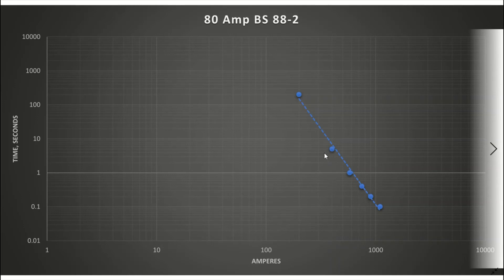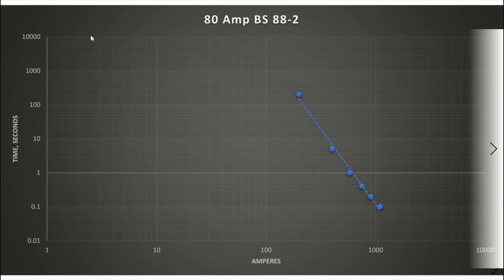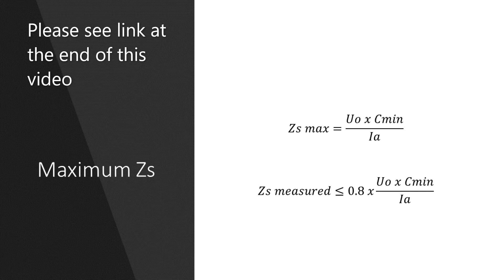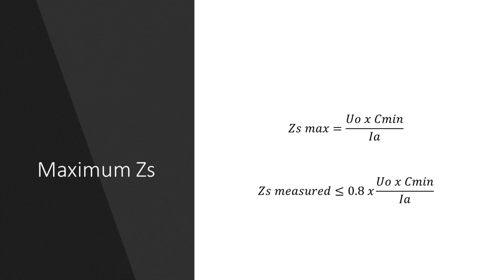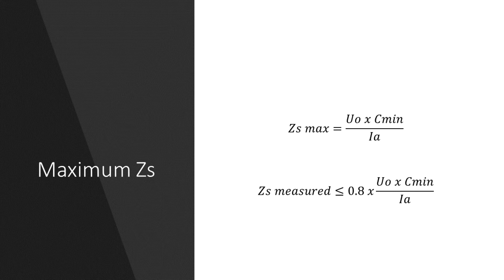So there are a few ways in which we can use the charts. Firstly we can use the charts to calculate the maximum ZS for a protective device by taking the minimum current required to meet the disconnection time, IA, and using the formula from Appendix 3. This is useful if using a protective device that isn't listed in the wiring regulations such as an MCCB and the max ZS is not listed in table 41. I talk about maximum ZS in another video on my channel and I'll put a link at the end of this video.